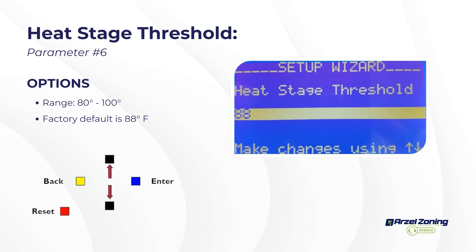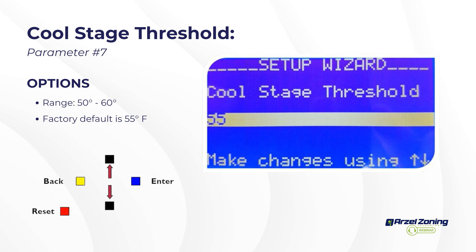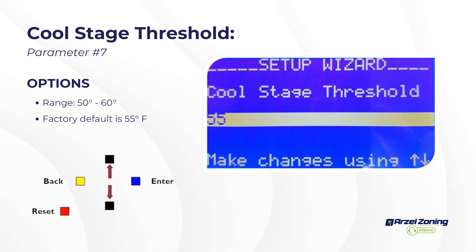For an all-electric system W1 is the next stage; otherwise the system switches over to the gas furnace. The cool stage threshold defaults to 55°F — if the air conditioner cannot maintain 55° leaving air temperature on Y1, it stages up to Y2 for second-stage compressor operation. This works independently of blower operation, so you can run a low-stage blower while running the compressor at a higher stage to remove or add more heat.